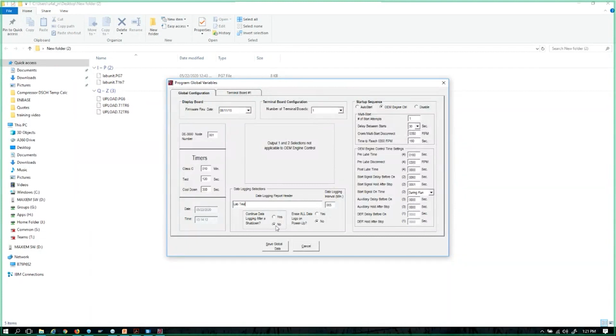So no is the preferred method here. Erase all data logs on power up. Well, this is another bad thing, because if somebody turns the unit off waiting on a senior level tech to get to site, and then that senior level tech gets to site, if this is selected as yes, any data log that's in the system is going to be erased. So again, these are the two defaults.